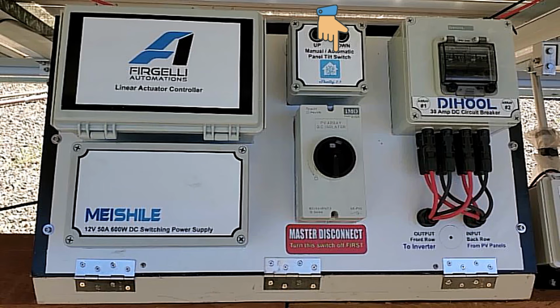At the top center of the unit is a feature I designed, a manual automatic panel tilt switch. Built around a Shelly 2.5 Wi-Fi controller, it includes 2 110-volt switching relays and 2 momentary push buttons. This setup allows for on-site panel adjustments even without a smartphone or internet access. In the bottom center is the IMO PV array DC isolator switch, a common component in most solar installations and a required element by code. It allows for immediate disconnection of the PV array in case of emergency or routine maintenance. To the right, you'll see the 30-amp DC circuit breakers for arrays 1 and 2, installed per the requirements of my inverters, which are MPP Solar Model LV6548.